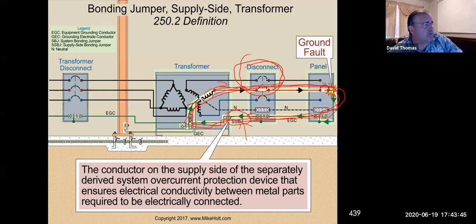that could actually explode. So for critical systems, we may be doing ungrounded systems, but in your house, in your commercial type applications, in the United States, we actually use this as the way our systems work, is that the equipment ground and these bonding jumpers have very specific applications in getting any electrons that go to ground fault actually go back to the source eventually and facilitate the operation of the breaker. Okay, so that's the first thing that you have to be aware of.